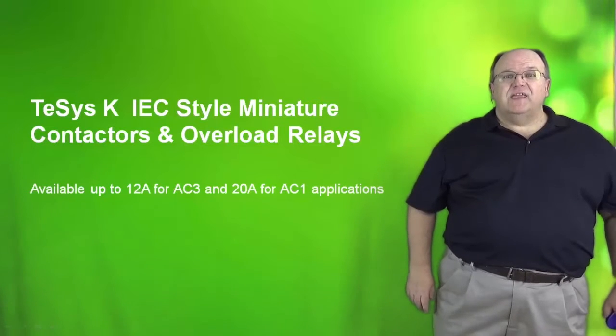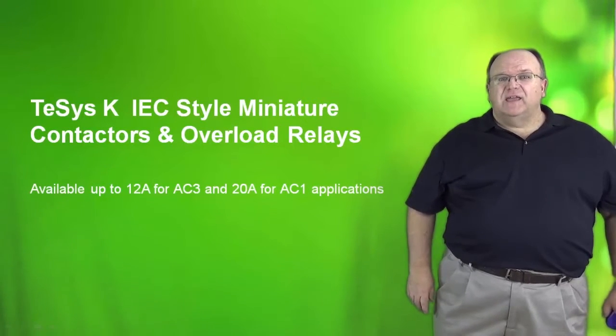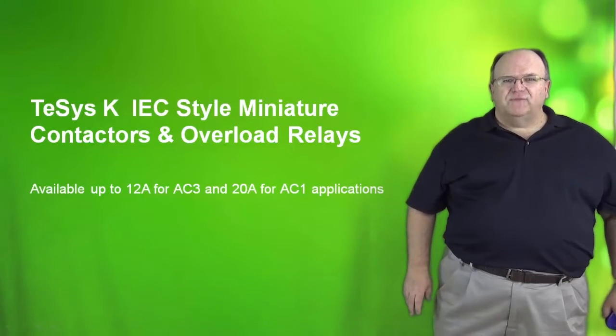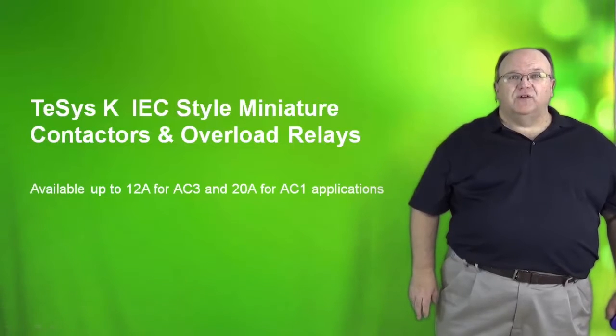The TeSys K is the smallest contactor in our IEC product family and it is available in three different sizes: a 6, 9, and 12 amp size for AC-3 or inductive loads. It is also available up to 20 amps for AC-1 or resistive loads.